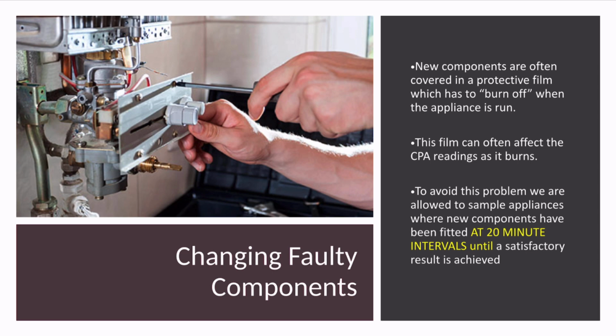If a new component, a new part has been fitted, or you've fitted a new part, or the assessor has put a new part in to an appliance you're testing, that part will probably have been covered in a protective film to stop it rusting or corroding or being damaged while it's sitting around on their shelf. When you light the appliance, the heat will start to burn off that protective coating. And the fumes that come off the burning protective coating will often affect your CPA readings.